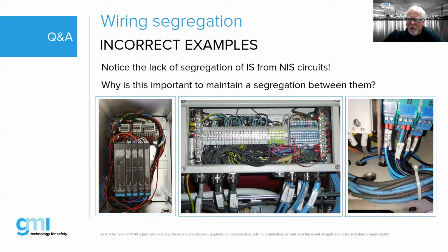So we have to make sure that we not only keep the devices separate by 50 millimeters, but the cables also need to be segregated by at least 50 millimeters, unless we're using some sort of shielded cable. That's generally pretty much a worldwide requirement. Armored cables, things like that, or shielded cables, we need to have segregation if we don't have some sort of shielding or armoring of our cables. So when you see on the very left-hand side that looping around, you know, service loops on the inside of a cabinet, that's a big no-no, because now all of a sudden we've defeated that 50 mil segregation.